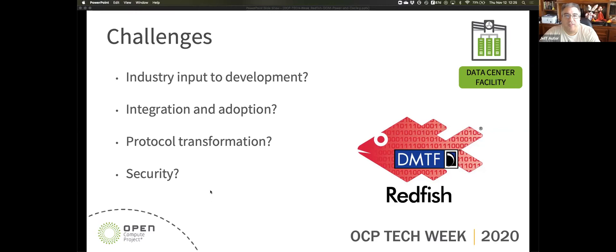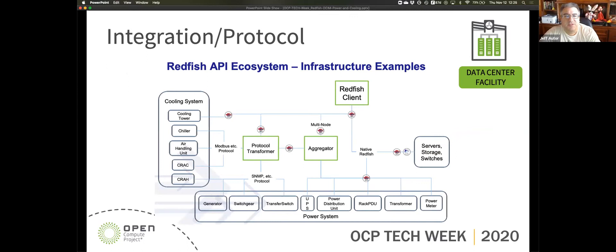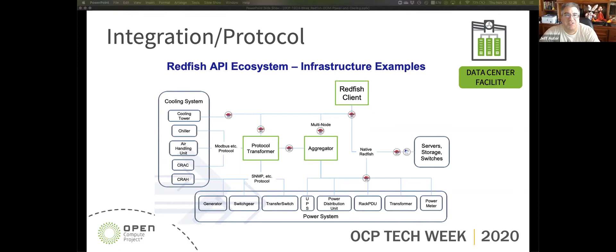There was also work being done by folks at Texas Tech on concepts for doing proxy or bridging applications where you could retrofit existing things like UPS units — providing a Redfish interface that acts as a bridge. I see that as probably the most viable way to get support into the general DCIM architecture, because this gear doesn't get replaced in the same life cycles as IT gear. If you wait 15 years for a full replacement cycle, something will have replaced Redfish twice over. So providing some proxy pieces — and making sure you're handling authentication controls and not suddenly giving people unlimited access to the BACnet or Modbus details behind it — is important.